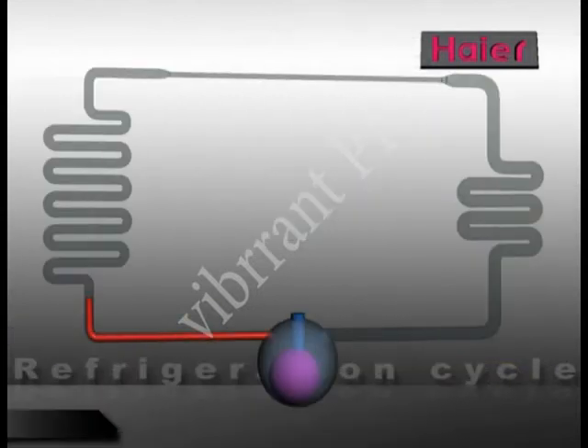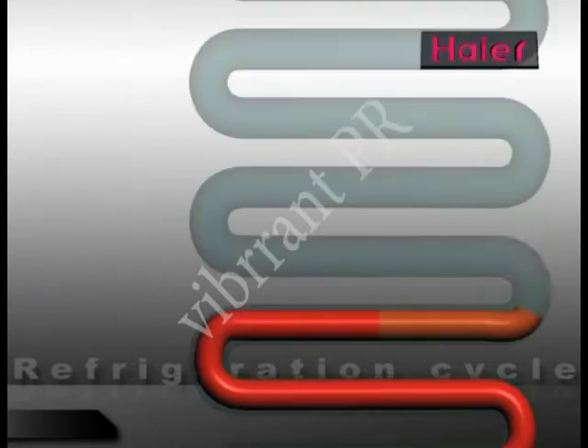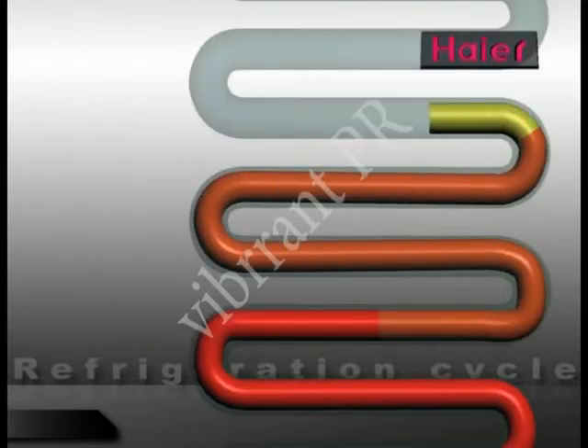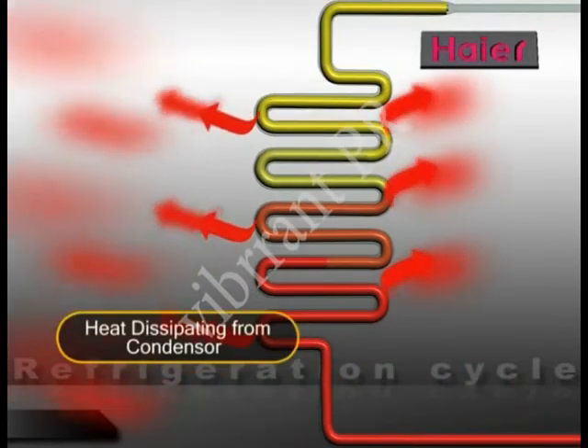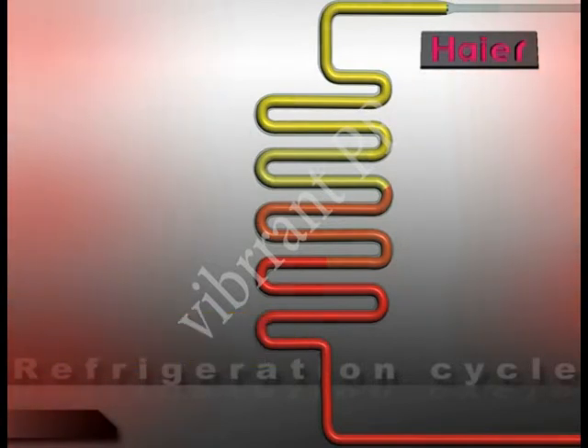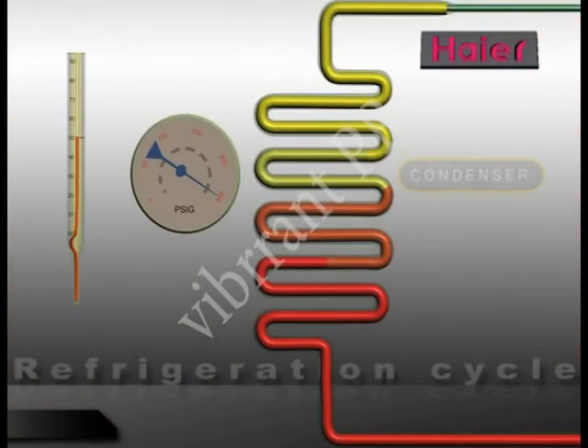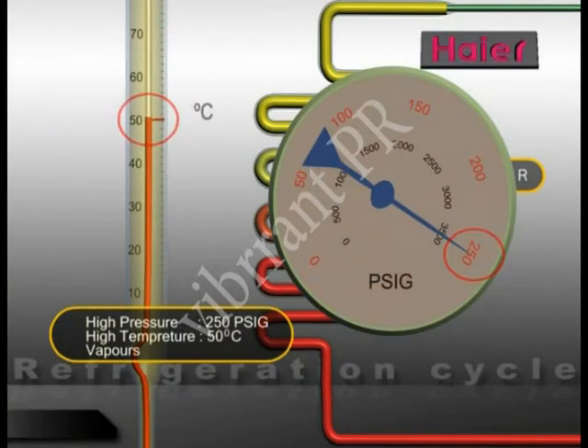These high pressure, high temperature refrigerant vapors from the compressor are passed into the condenser. In the condenser, the high pressure, high temperature vapors give out heat into the atmosphere and cool down into a high pressure refrigerant liquid. The temperature of this high pressure liquid is approximately 15 degrees more than the ambient temperature.